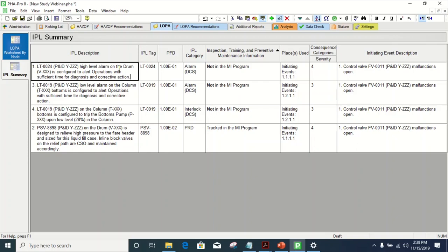When you think about a HAZOP, two things that are pivotal: one is that you identify key failure modes in terms of the causes identified within a HAZOP, and you also identify when a safety feature is needed or when it's missing. If you apply those two ideas to a mechanical integrity program, that is already a good basis for a well-integrated MI program. The importance of those two ideas is that you're already doing them as part of the HAZOP, and if you can document the HAZOP in a clean and well-organized manner, it's easy to apply it to your mechanical integrity program.